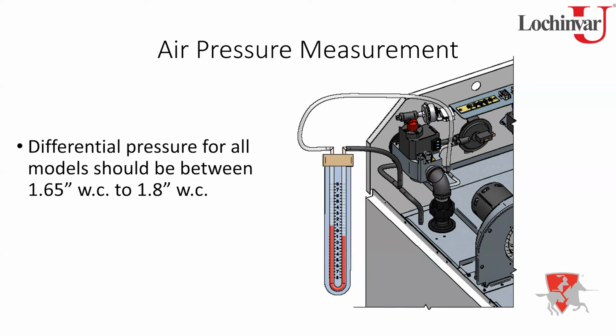The heater might light, but typically what you're going to end up with is a hard start or a rough ignition, because now I've leaned that gas-air mixture out too much. I'm putting way too much air down into that combustion chamber than what I really need. So a lot of times when this thing goes off on low air, in most cases, what you're dealing with is something putting a back pressure on the burner. Some type of blockage, a dirty burner, a sooted heat exchanger, a venting issue, something of that nature is more often the cause of an air pressure switch lockout condition.